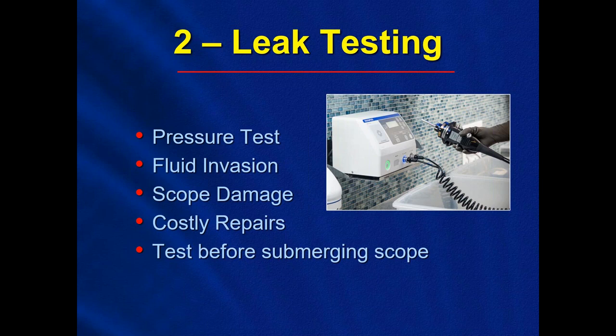Now, SGNA, the Society of Gastroenterology Nurses and Associates, recommends that leak testing be done before the scope is submerged to reduce the risk of fluid invasion. And you must always follow your scope manufacturer's IFUs for leak testing. Again, a pressure test, checking for fluid invasion and compromise to the scope.